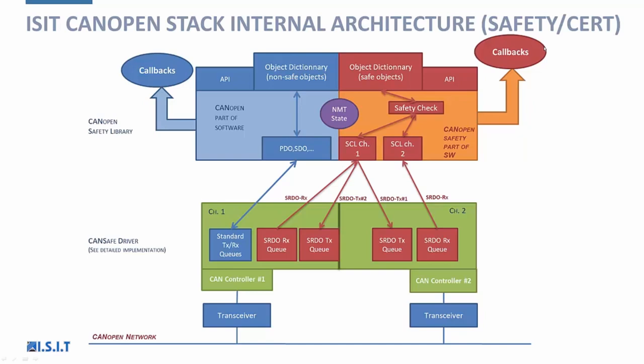The first CAN channel is used for both standard CAN Open messages and safety messages, while the second is used only for safety messages. The model choice must be decided based on the necessary hardware architecture and safety level needed, and we can adapt the stack to any model on demand.